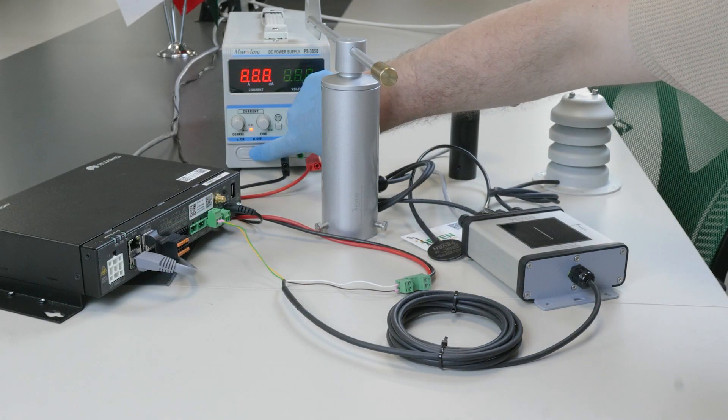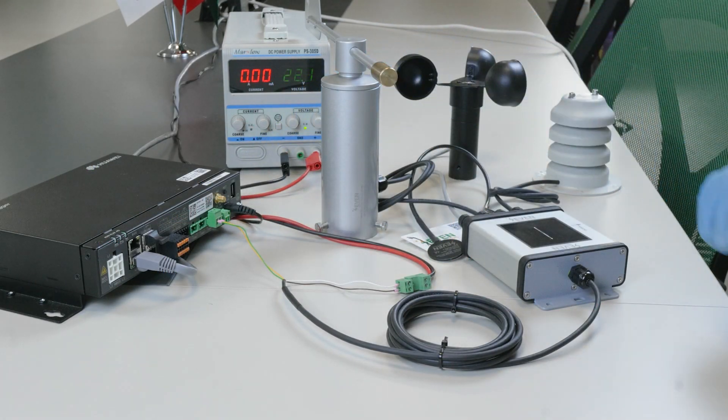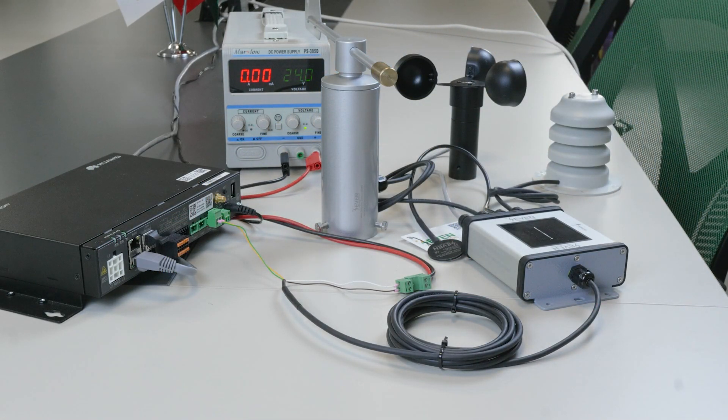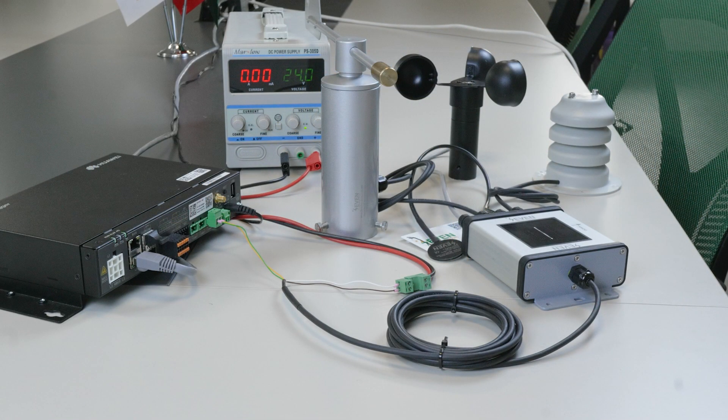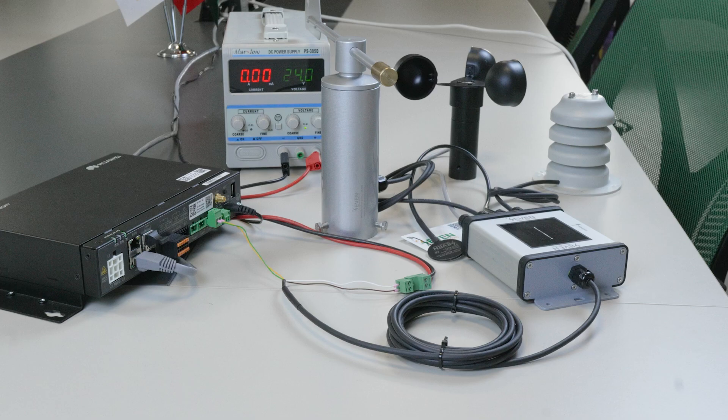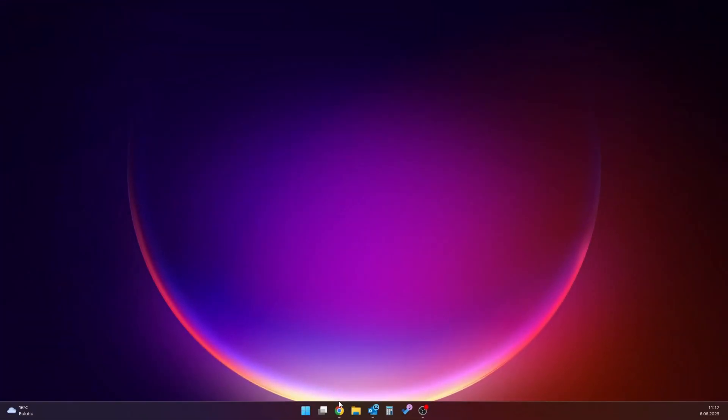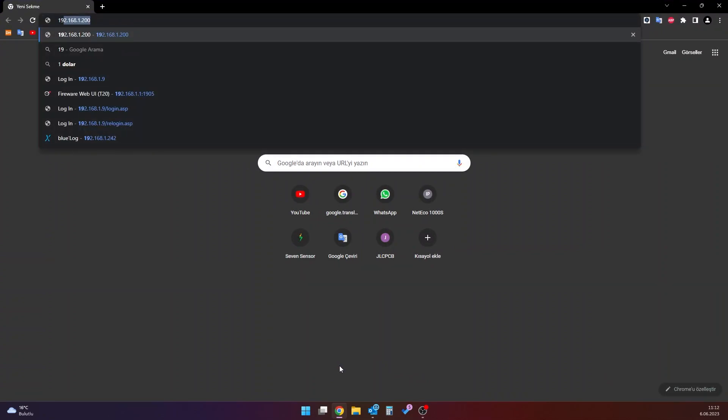Once the connection cable between the data logger and the sensor is completed, the sensor must be added to the data logger. There is an internet browser interface for this process. To connect to the data logger interface, the computer to be used and the data logger must be connected to the same network. A web browser opens on a computer on the same network as the data logger. A search is made by typing the IP address of the data logger into the web browser.